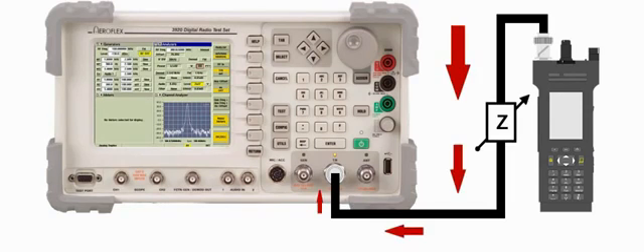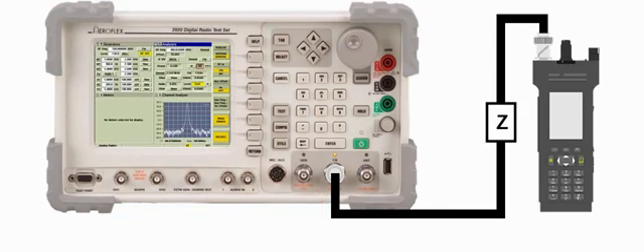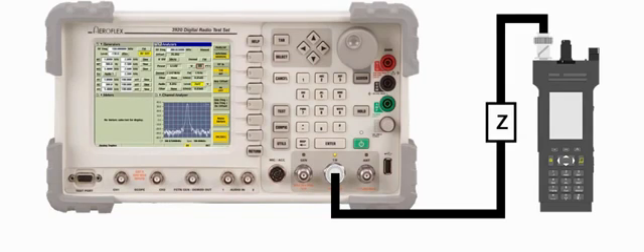This loss reduces the amplitude of the signal and will produce a power measurement lower than what the transmitter is actually generating. Therefore, in order to measure the true power of the transmitter, we must determine how much cable loss is present at the transmitter's frequency.